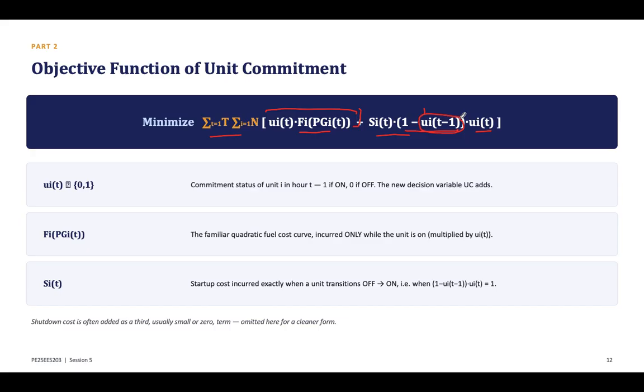See, the objective shown is intentionally compact here. A more complete formulation may include shutdown cost and fixed maintenance cost, reserve procurement cost, emission costs, fuel constraints, and penalty terms. The compact form is still sufficient to expose two fundamental cost types: the cost of remaining in a state and the cost of moving into a state. It might be the on state or off state, anything. So the constraints in this formulation should not be treated as independent add-ons. They interact.